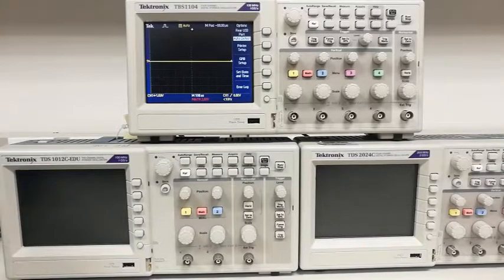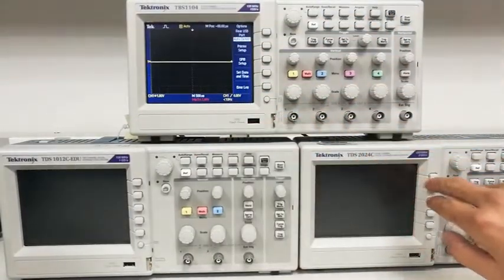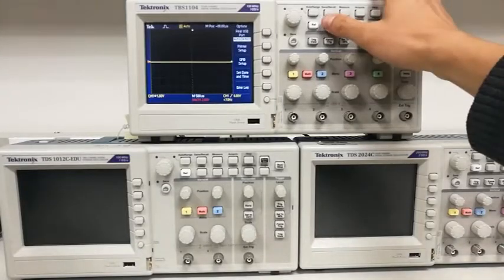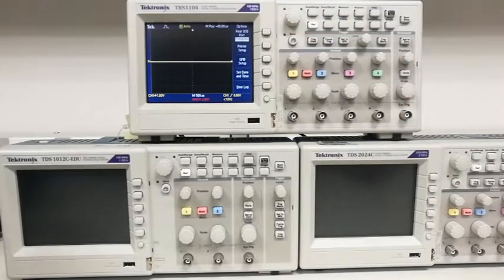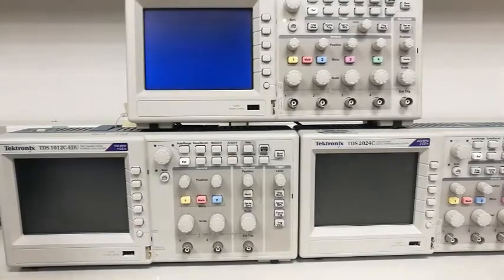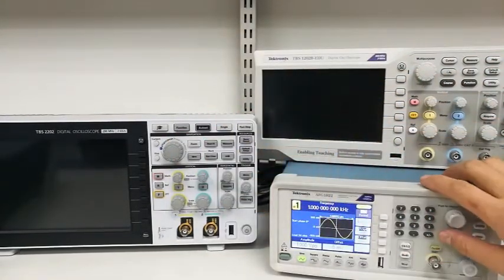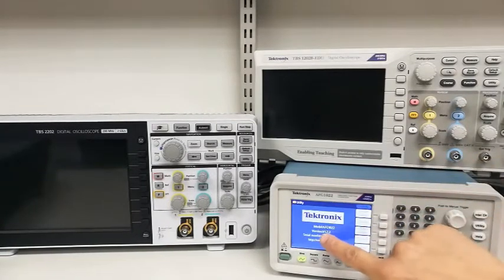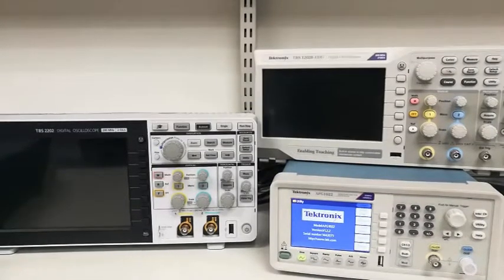If the instrument cannot turn to green, or some features cannot work properly in the software, please check their settings and their firmware. For TBS1K, TDS1K, 2K series oscilloscope, press the utility button and change their USB port to be computer and reboot the instrument. For TBS1K-EDU, TBS2K oscilloscope, and AFG1K series, their firmware should be upgraded to the latest version available on TekSmartLab's website.